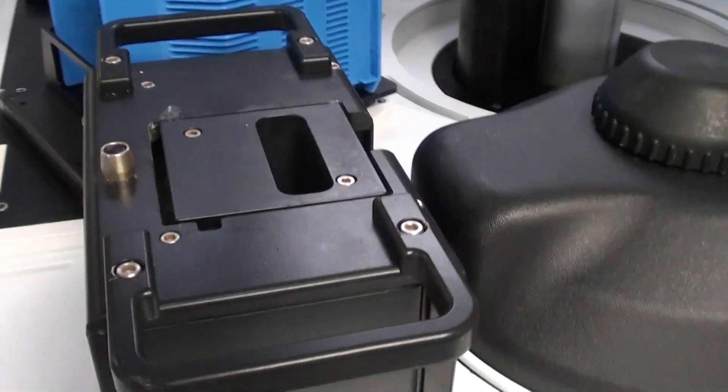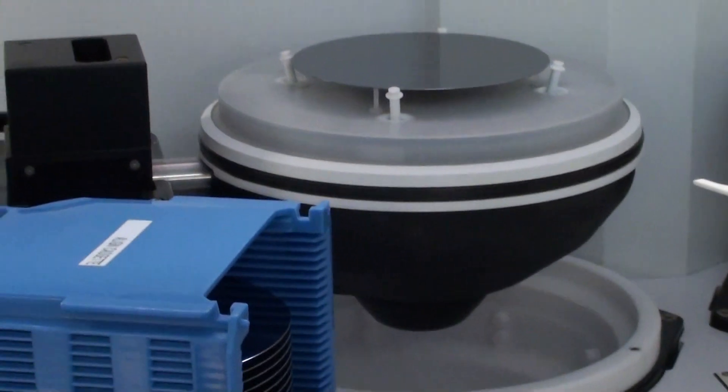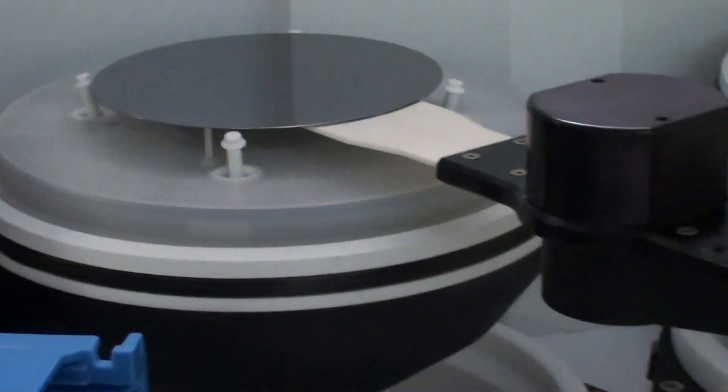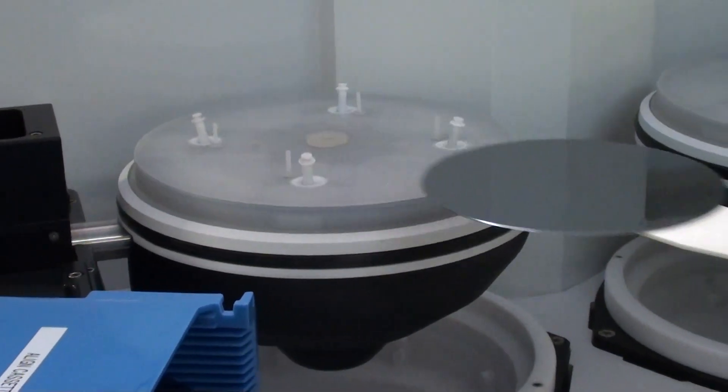We've gone through it from the pneumatic lines to the cabling to the bearing slides, all the way back to the rotor. Each one of these rotors has been pulled and all the hardware on the backside has been replaced. All the springs and clips, any of your typical wear items.